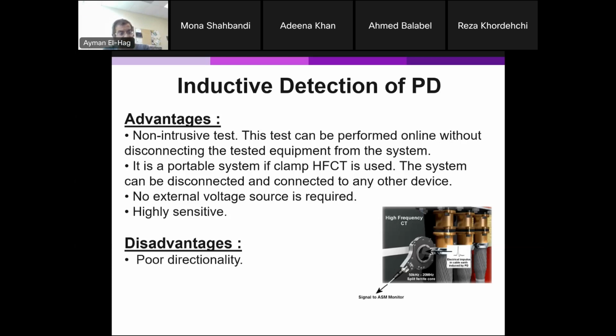There are certain disadvantages: poor direction. You can't find the direction. You know that it can't also be used for localization. You know there is a partial discharge inside the transformer, but where it comes from, whether from the core or the winding, which phase, you cannot tell. And you have to have direct access to the ground. Sometimes you don't have access to the ground. It's not easy, so you cannot implement this. The last disadvantage is that it has a very low signal to noise ratio.